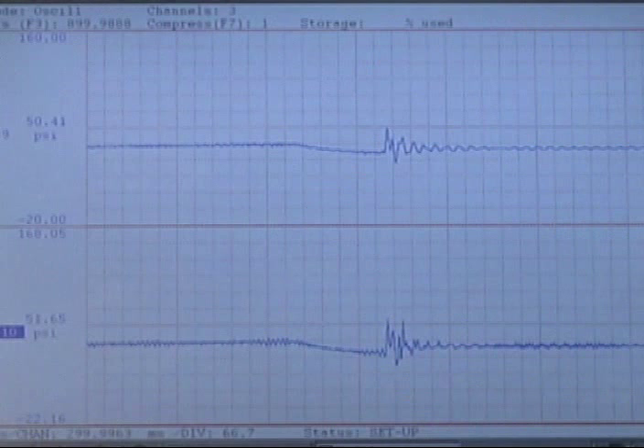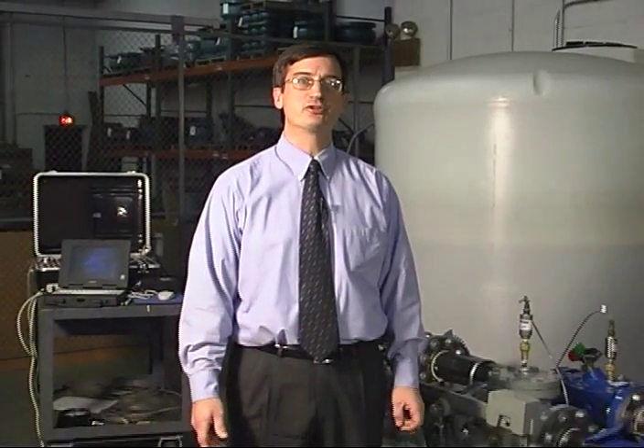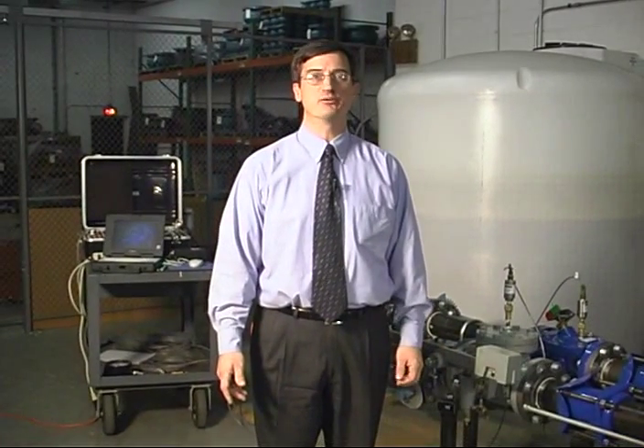And there we have silent closure of the surge buster check valve. This test demonstrates the superior non-slam characteristics of the Valmatic surge buster check valve as opposed to the traditional air cushion lever and weight check valve.